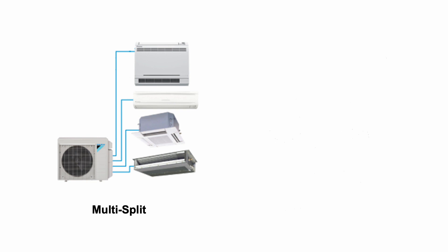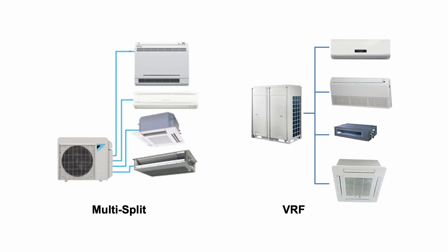Whereas for VRF system, we also can use one outdoor unit connected to multiple indoor units. But the difference is, each indoor unit has one pair of refrigerant pipe that connects with the second indoor unit, then goes back to the outdoor unit. Basically at the outdoor unit, you only have one pair of refrigerant pipe. At each intersection, we use this Y-joint to connect the copper pipe. This Y-joint is only used for VRF system.